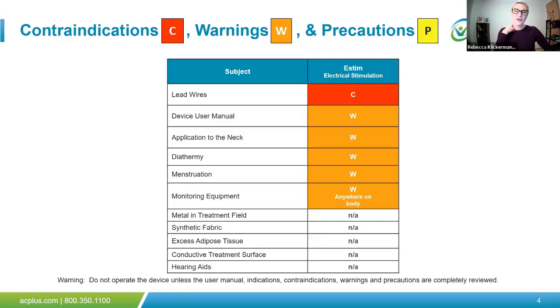Diathermy, especially if you're using head and neck PENS in a busy gym, you want to ensure that diathermy is not in use in close proximity, and that would be defined as less than 5 feet. You always want to ensure there's some space between a patient receiving diathermy and your patient receiving PENS.